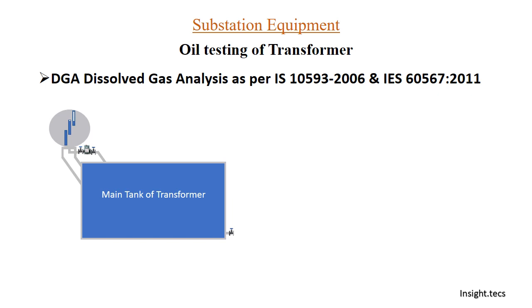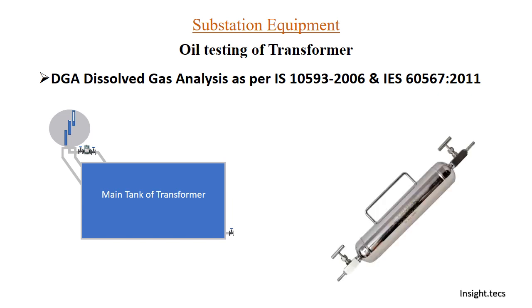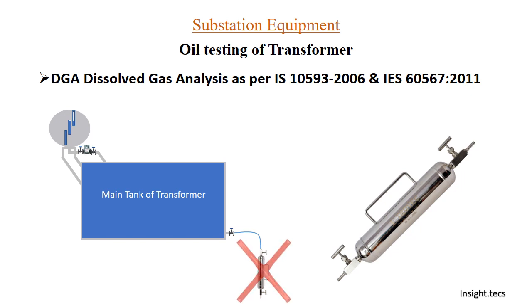For DGA testing — dissolved gas analysis — we have to use a steel bottle. Unlike the glass bottle, we do not take the sample with the steel bottle in the downward position, because it can introduce air bubbles. You should always avoid taking samples with the bottle facing downward for DGA.